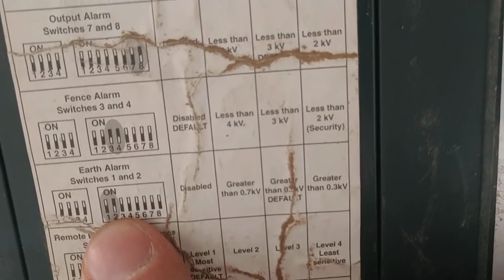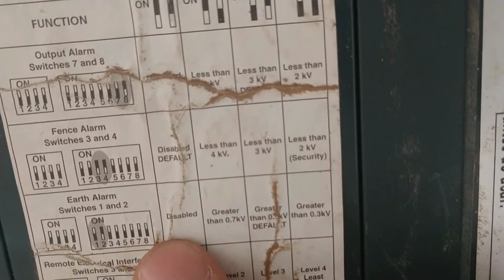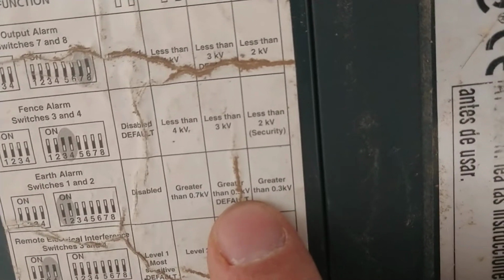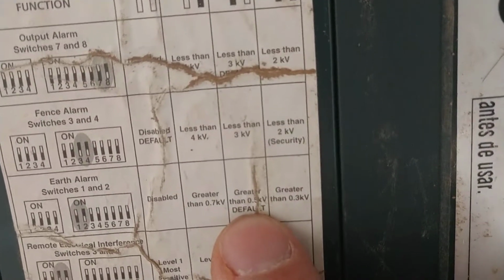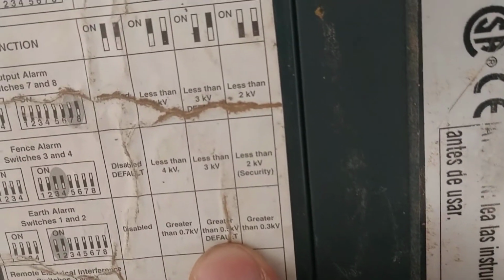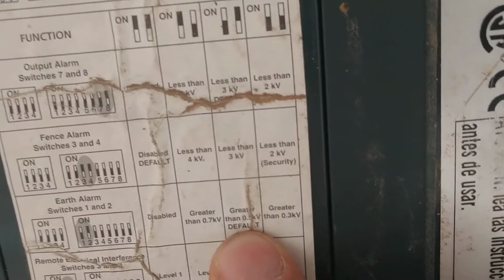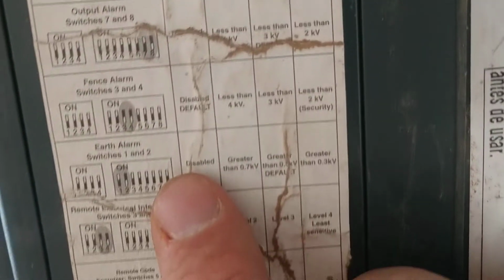See, for switches 1 and 2 on the set of 8, the default setting is turned on, and it says if the voltage on your ground side is greater than 0.5, that alarm will go off. But that's on your earth alarm.